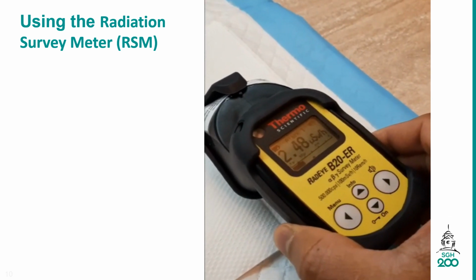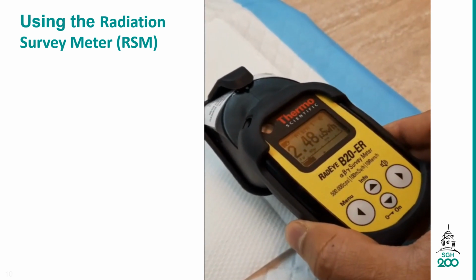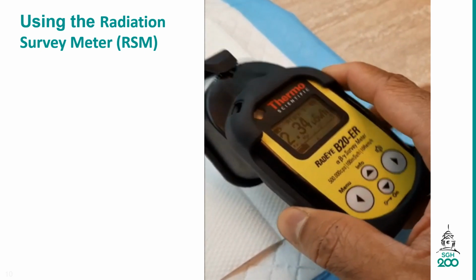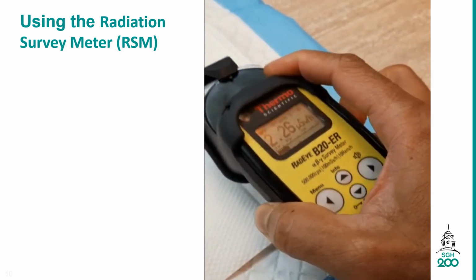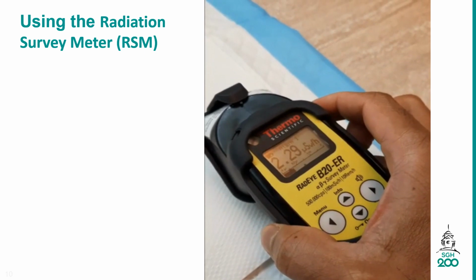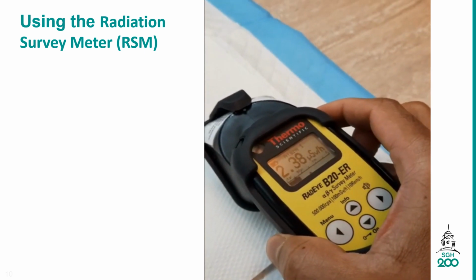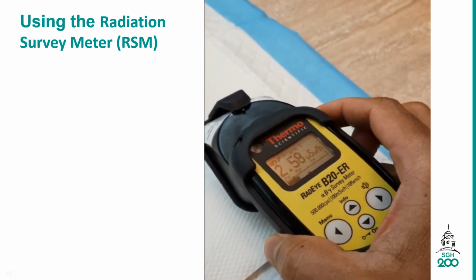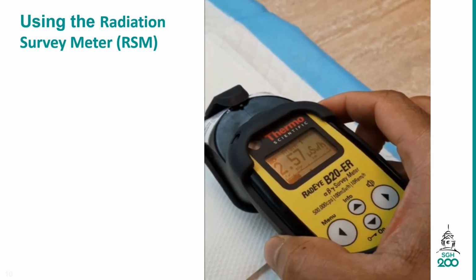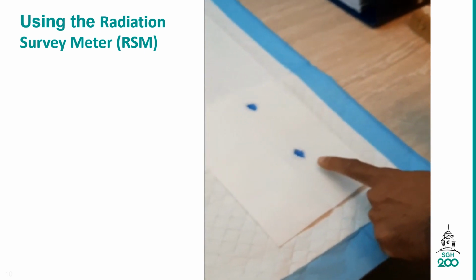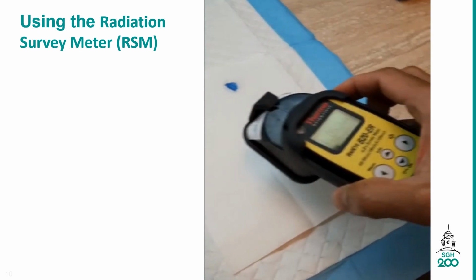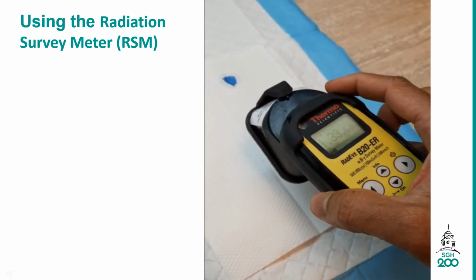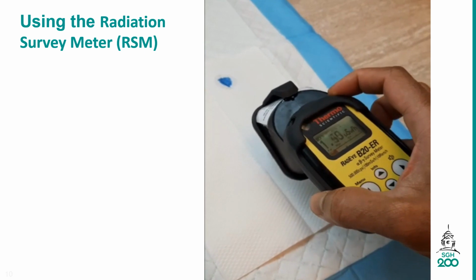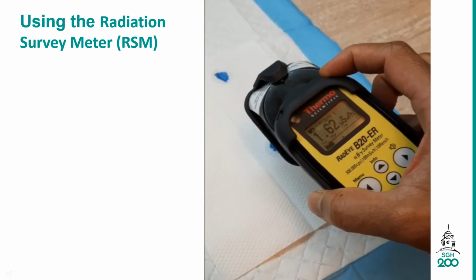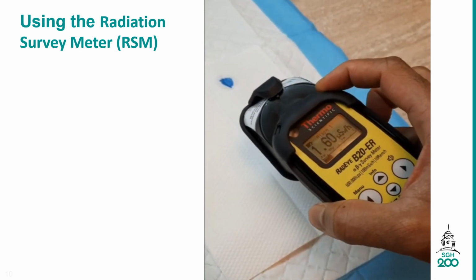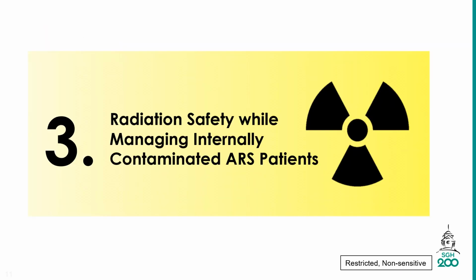Oh wow, there is some radiation. So this is what the patient will be. Let me switch off the sound, so that you can hear me. This is basically we are reading something like 2.4 microsievert per hour at 5 centimeters away. So just imagine if that was your patient, that's the 5 centimeters that you will be measuring the radioactivity of. The cutoff is 10 microsievert per hour, right? So if you have never reached that sort of levels at this distance.